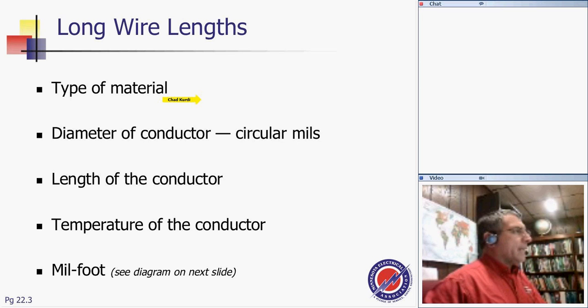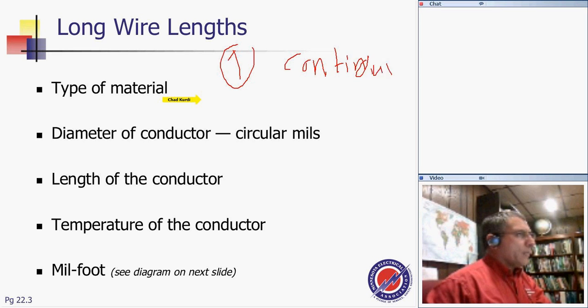We'll take a few examples, guys. But before the examples, here's how we size conductors for any system. There are two ways we size conductors. Number one, based on whether the load is continuous. Number two, based on derating. Do I need to derate? Are there derating factors based on the rating?